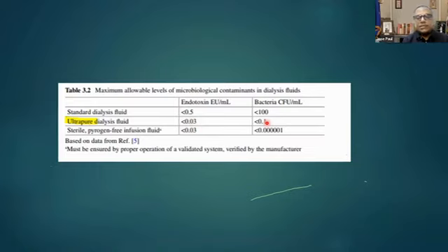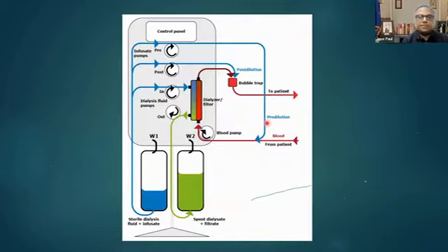There are no tests able to detect these; they are in general undetectable by the standard tests. You cannot demonstrate an endotoxin or a bacterial colony count in this ultra pure water. Such a high degree of sterility of the dialysis fluid is required if you want to do this procedure.